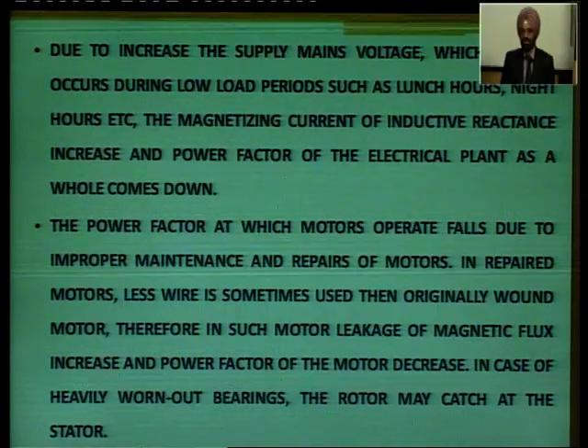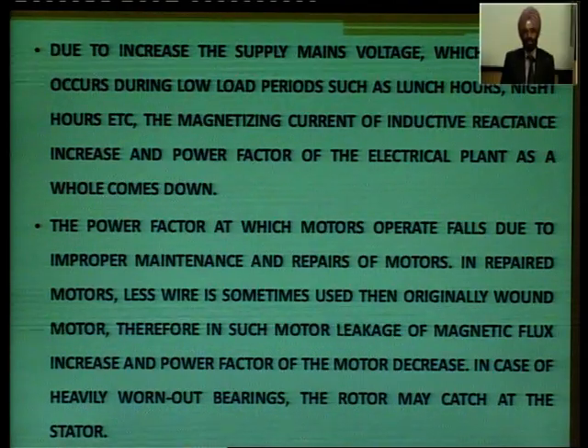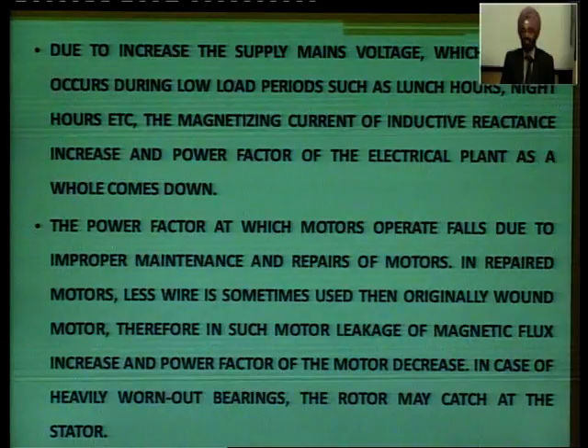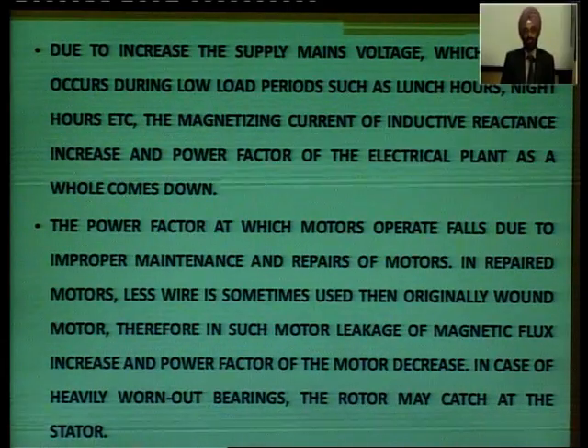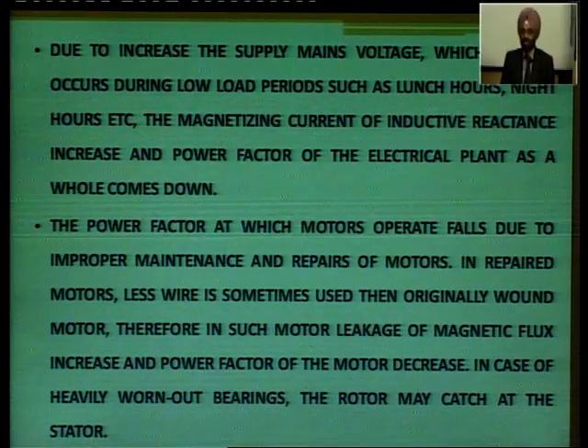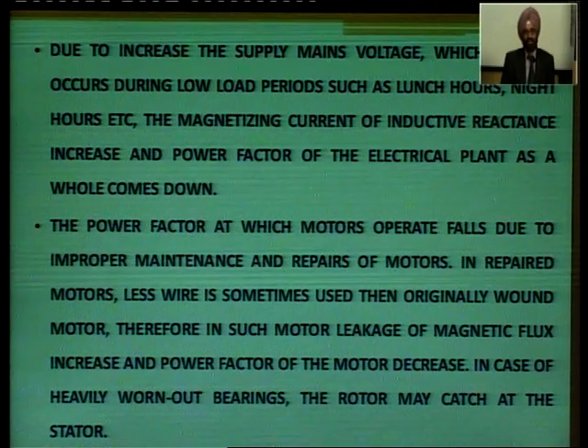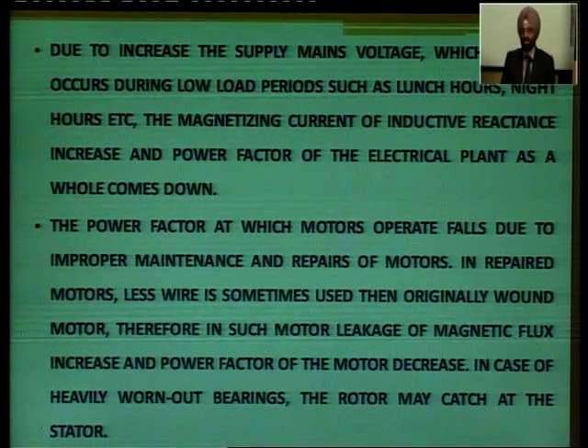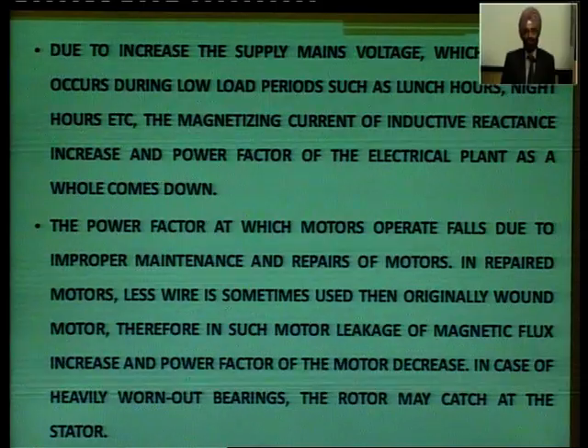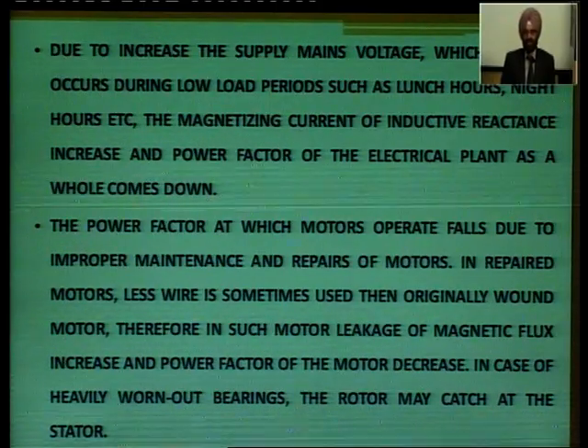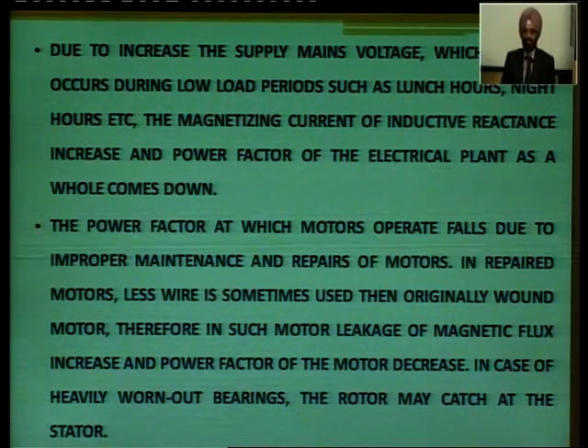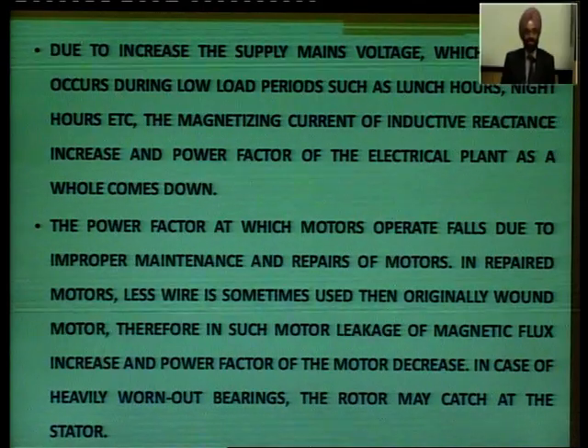you can study in the case of a transformer, the magnetizing current always lags the voltage by 90 degrees, exactly lags the voltage. So magnetizing current is purely inductive current. So as we go on increasing the magnetizing current, the power factor goes on decreasing. So the next cause is that the power factor at which motors operate falls due to improper maintenance.